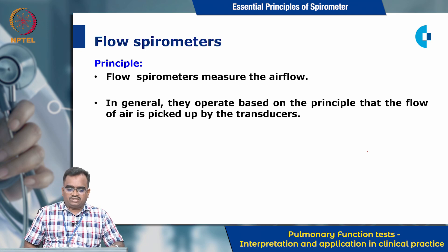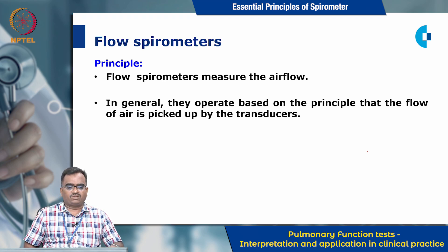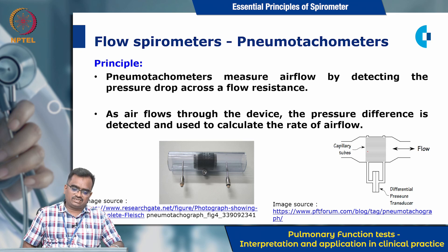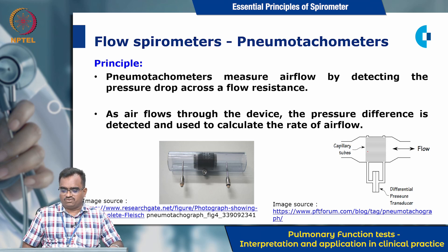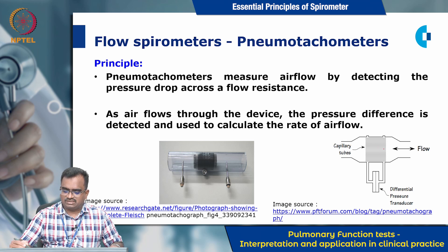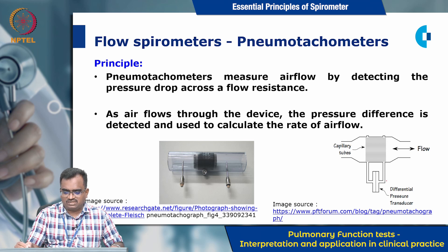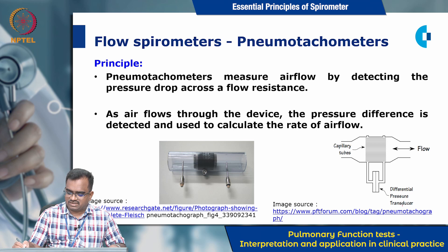Flow spirometers measure airflow. In general, they operate based on the principle that the flow of air is picked up by transducers. An example of a flow spirometer is the pneumotachometer, which measures airflow by detecting the pressure drop across the flow resistance. As air flows through the device, the pressure difference is detected by differential pressure transducers and used to calculate the rate of airflow.